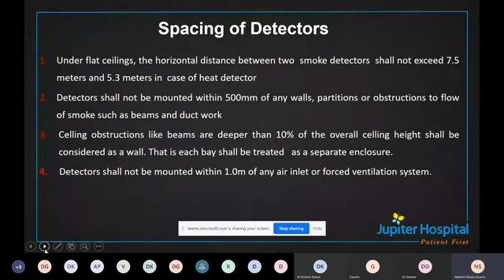Similarly, if there is an obstruction like deeper beams, consider the case where most of the time the beam is somewhere around more than 400 mm and the overall ceiling height is only 3.5 meters. So the beam size is more than 10% of that. In that case, we need to consider the beam as a wall, treat it as two different bays, and put two different detectors there. Then a detector shall not be mounted within 1 meter of any air inlet or forced ventilation system. So if there is an air inlet or forced ventilation system, we should not mount anything within 1 meter of that area.